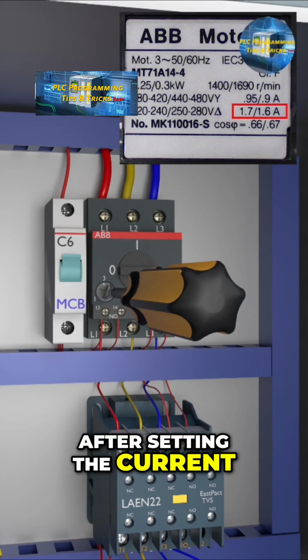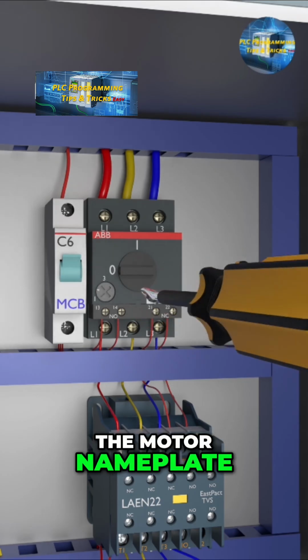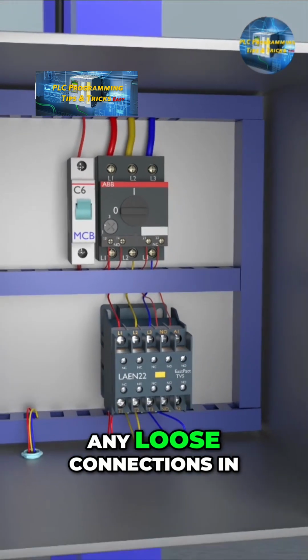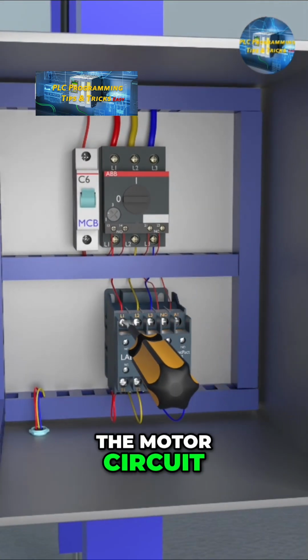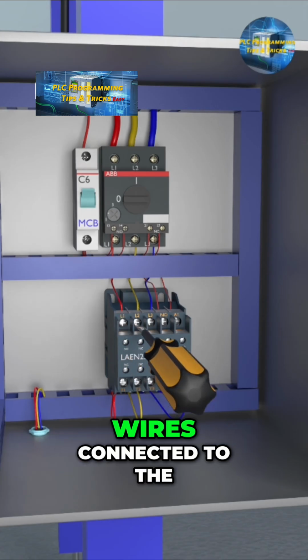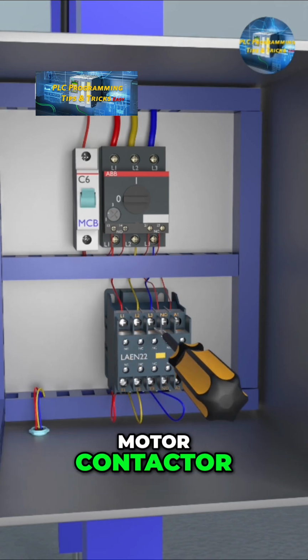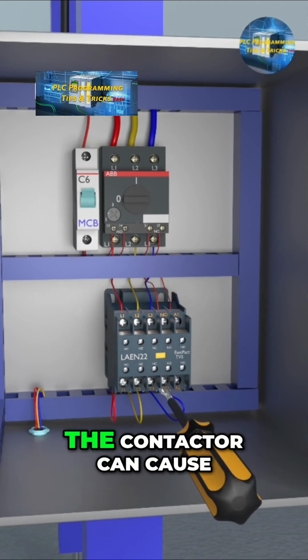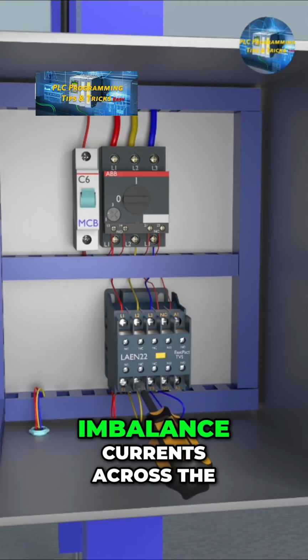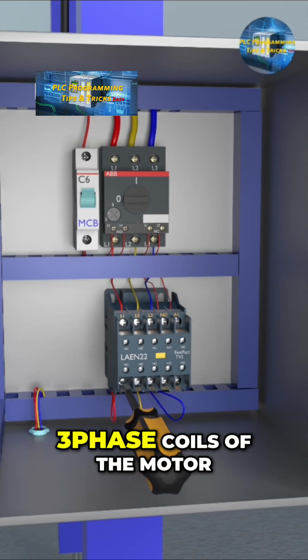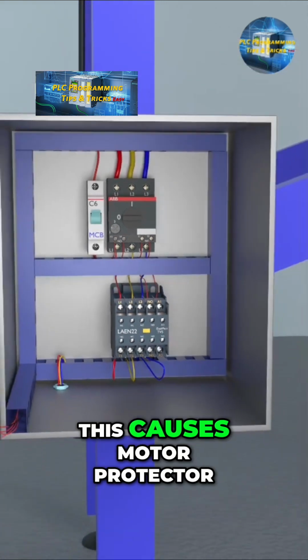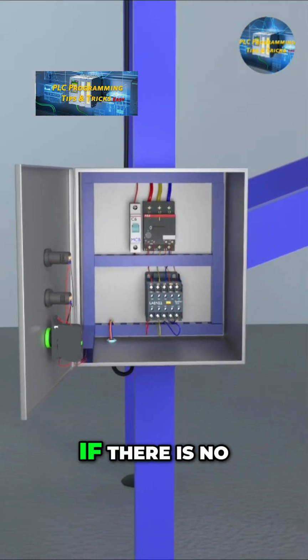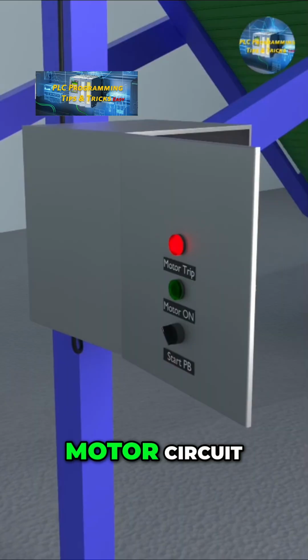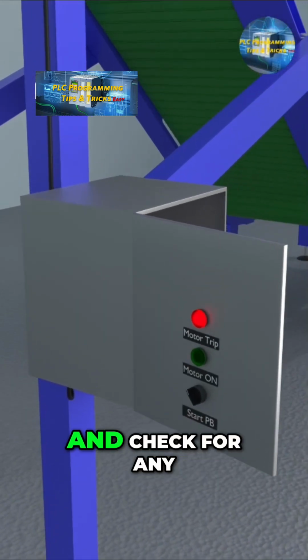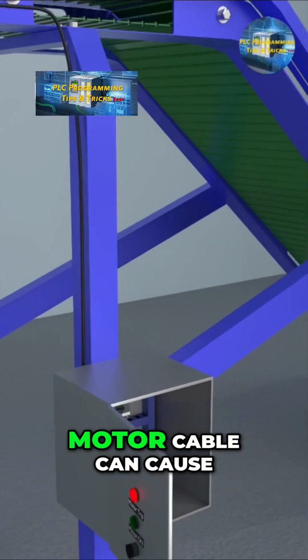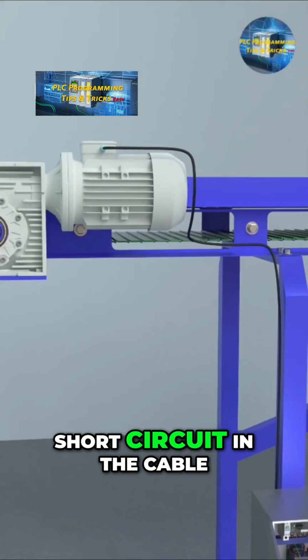After setting the current limit properly as per the motor nameplate, we can look for any loose connections in the motor circuit. You can inspect the wires connected to the motor contactor. Loose wire connections in the contactor can cause imbalanced currents across the three-phase coils of the motor. This causes the motor protector to trip. If there is no loose connection in the motor circuit, we can move forward and check for any physical damage to the motor cable, which can cause a short circuit in the cable.